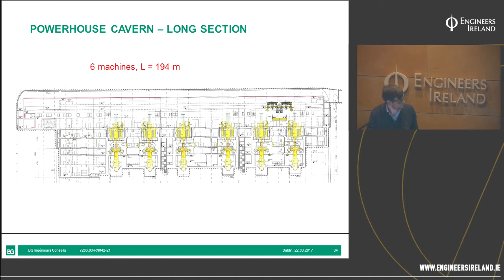Just a couple of words about the machine itself. It's an asynchronous variable speed Francis pump turbine, vertically mounted. One of its particular features is that it has a spherical valve above and below. The reason for the spherical valve below is the very high downstream pressures due to the level in the lower lake, which is quite unusual.